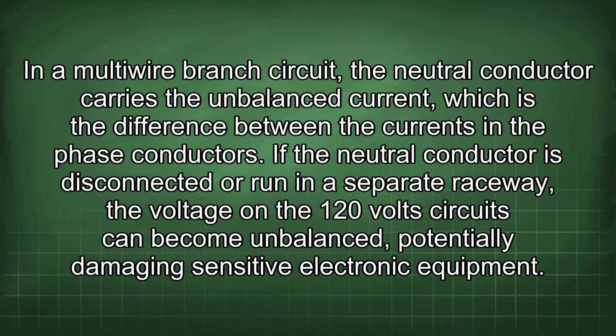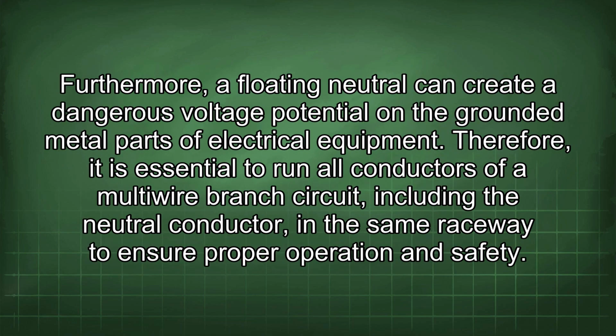the phase conductors. If the neutral conductor is disconnected or run in a separate raceway, the voltage on the 120-volt circuits can become unbalanced, potentially damaging sensitive electronic equipment. Furthermore, a floating neutral can create a dangerous voltage potential on the grounded metal parts of electrical equipment. Therefore, it is essential to run all conductors of a multi-wire branch circuit, including the neutral conductor, in the same raceway to ensure proper operation and safety.